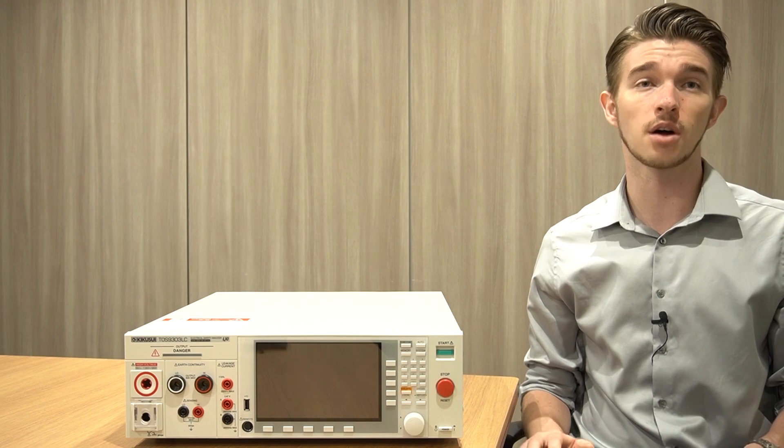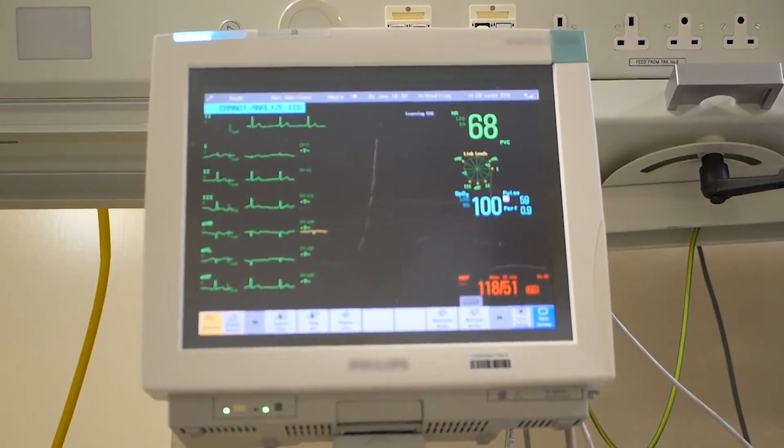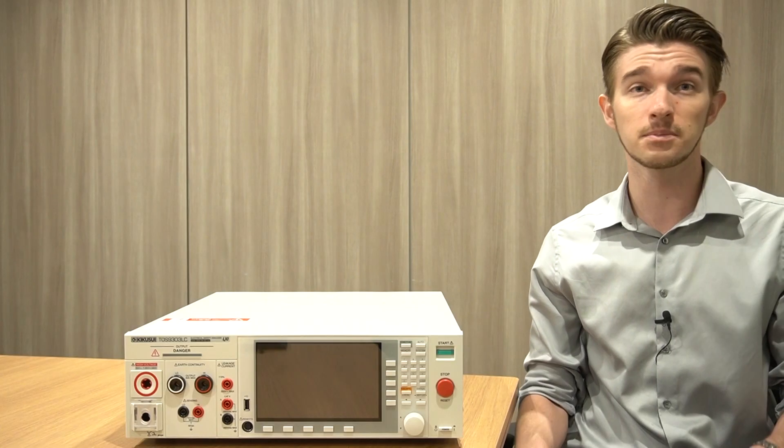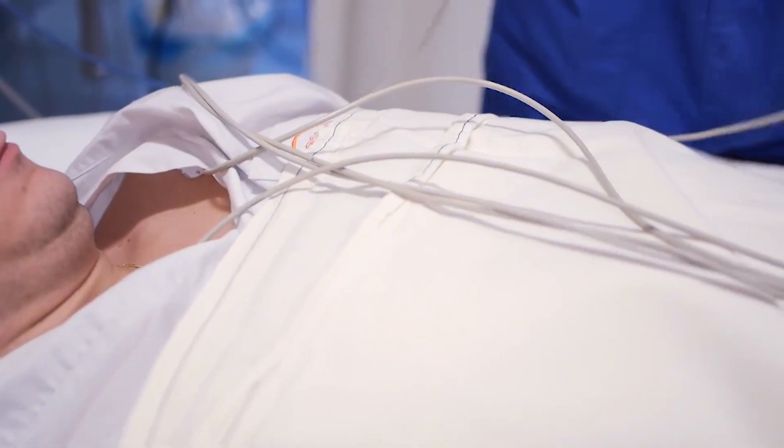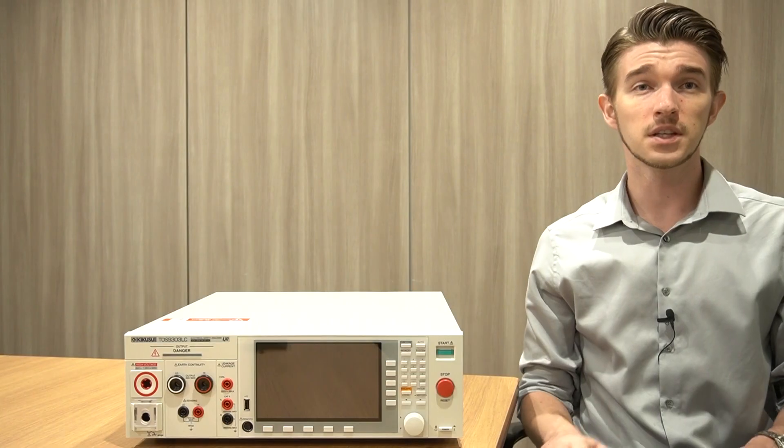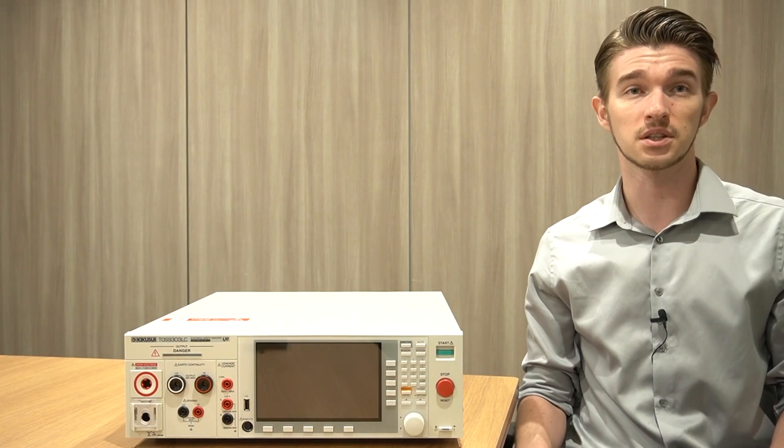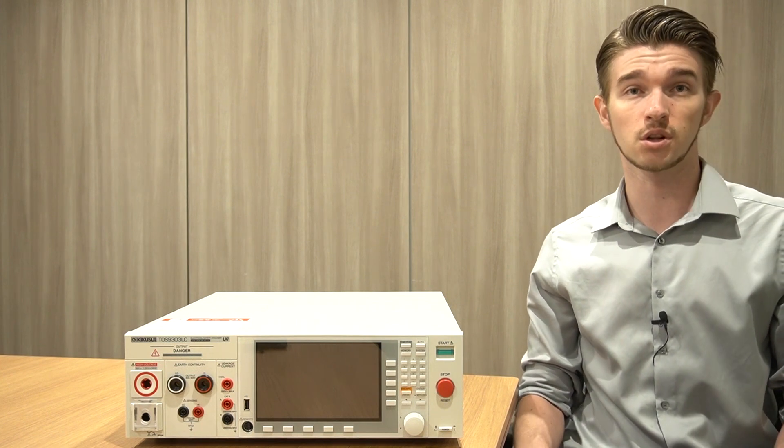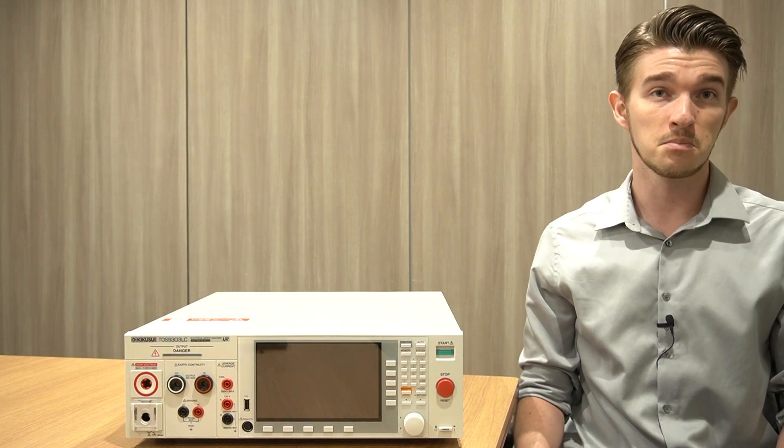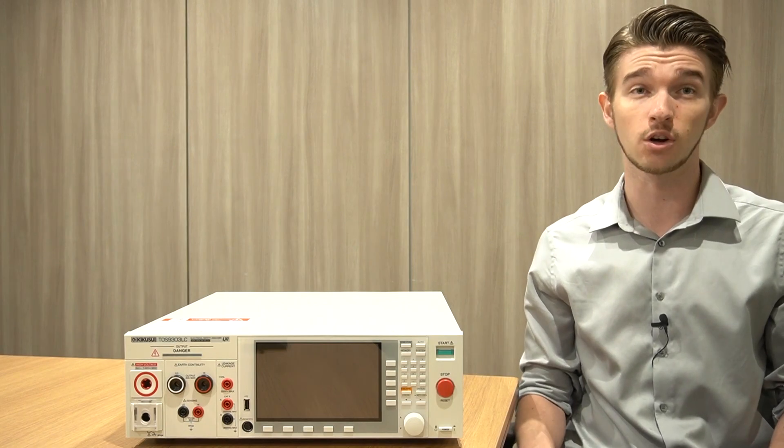Medical devices often have active parts inserted into the patient body and they sometimes come into direct contact with sensitive organs like the heart. This makes already susceptible patients even more vulnerable to electrical hazards such as leakage current, meaning that stringent electrical safety testing is critical.